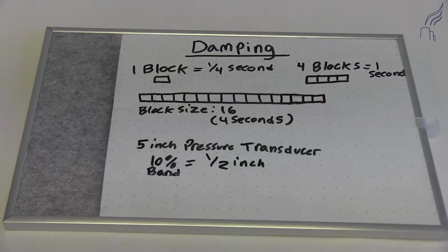Damping allows pressure transducer readings to be broken into blocks of readings and averaged. Damping is useful for testers because conditions may provide sporadic values to appear on the screen that change too fast for a tester to read accurately. Averaging the readings through damping allows a more stable value to be read on the console that is also representative of the test conditions.